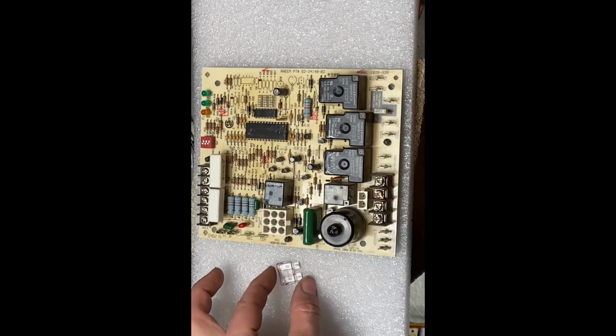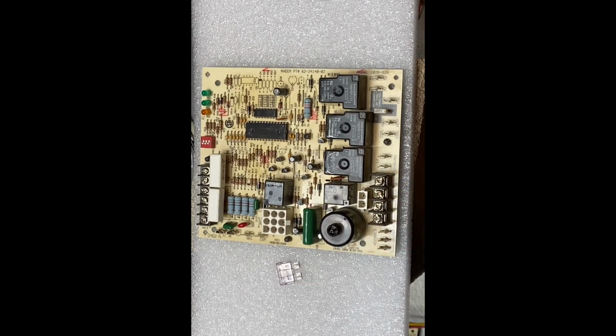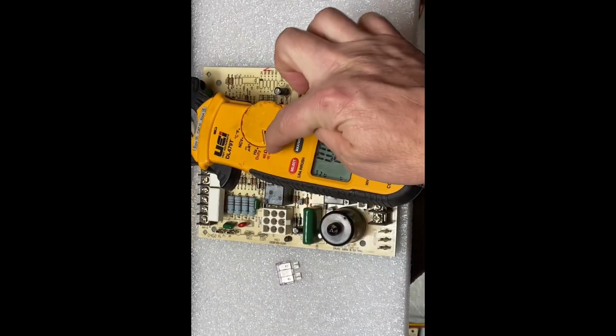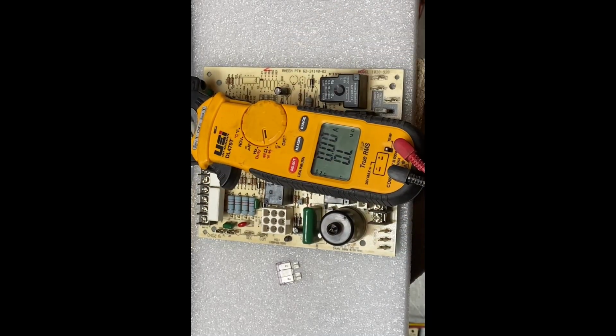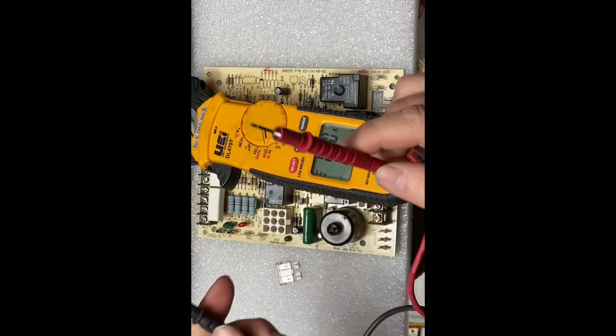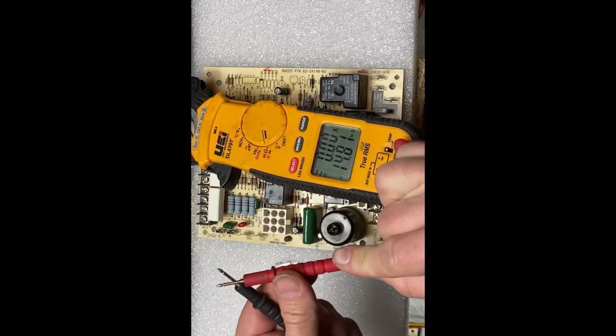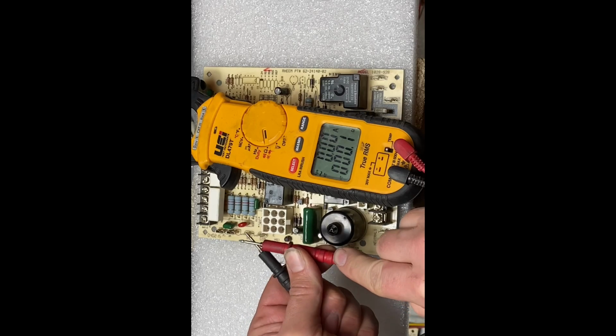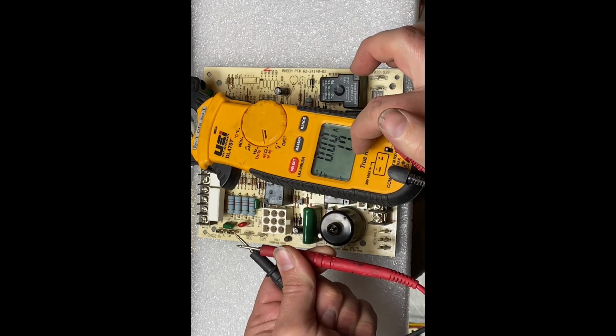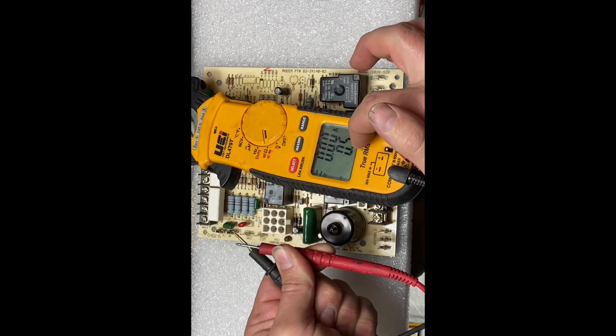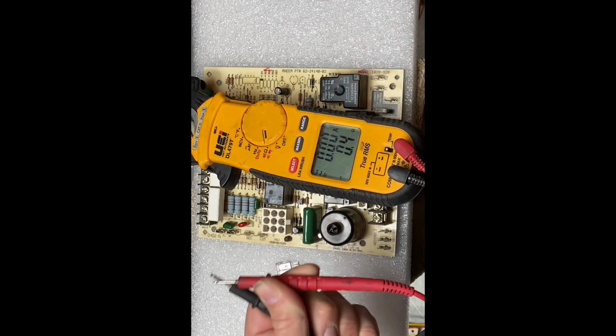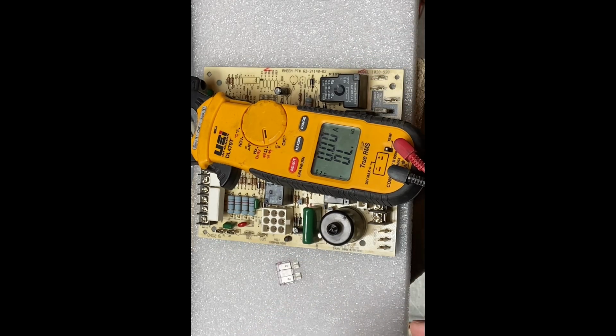So if you look on this fuse, there's this big black spot right here. It's burned out. Now there's a few ways you can check it. If it's powered up, you can check voltage across it. If you're reading voltage, then you have a blown fuse. If there's 0 volts, then you know the fuse is good. But I'm going to set my meter for ohms, and what we can do is actually check this. So before I check the fuse, I check my meter, I push the 2 leads together, and I can see how good my meter is working. And right now I'm showing some number of ohms for resistance. So that tells me my leads probably have some kind of damage on there.